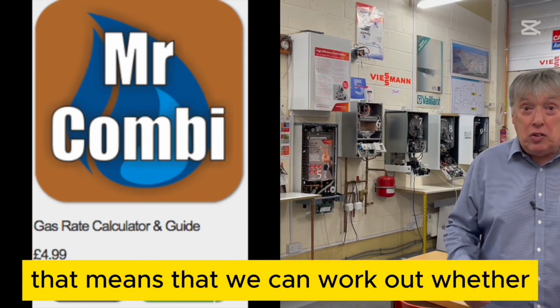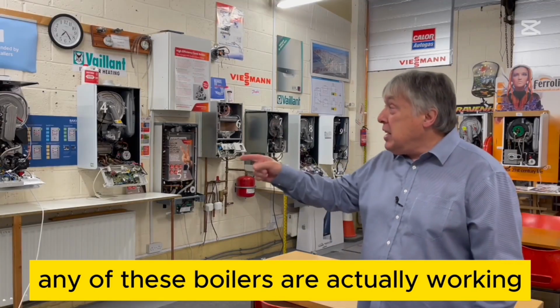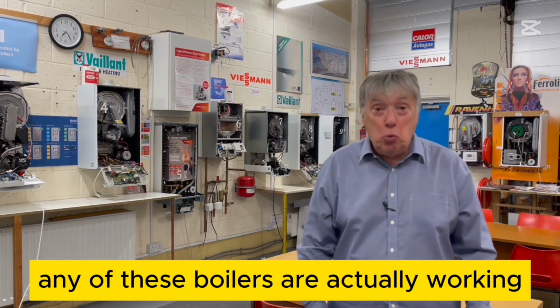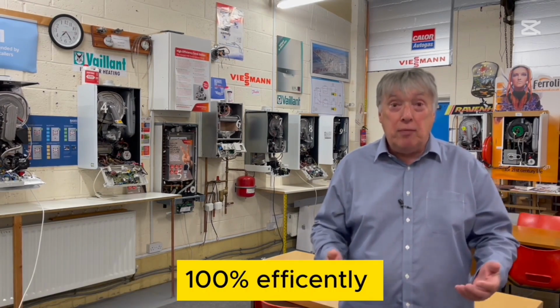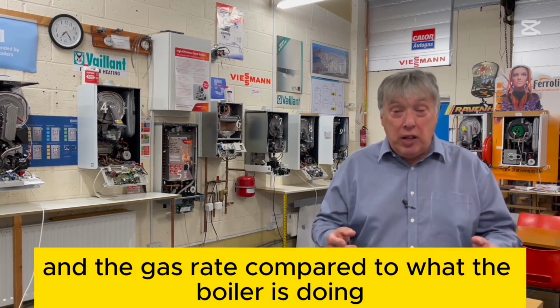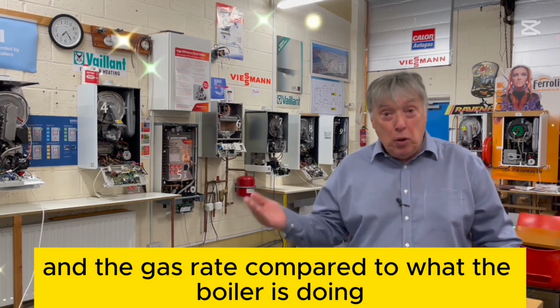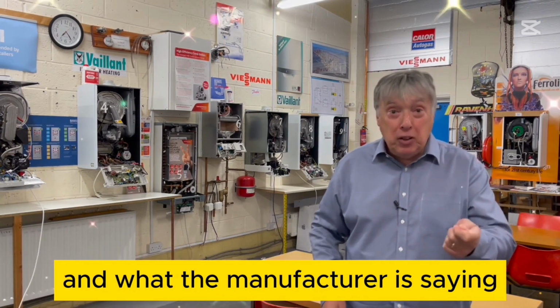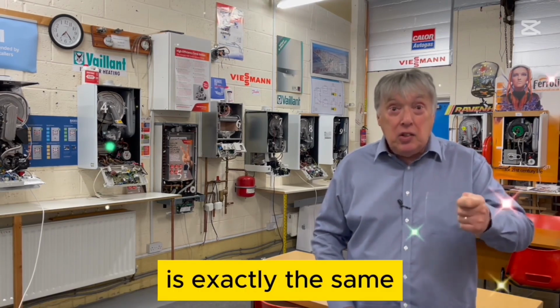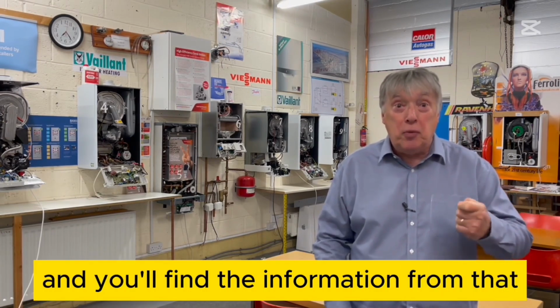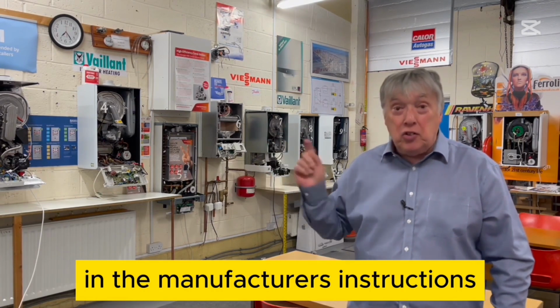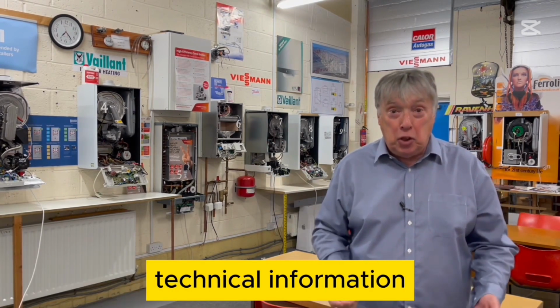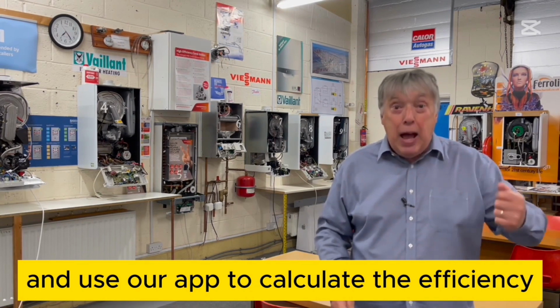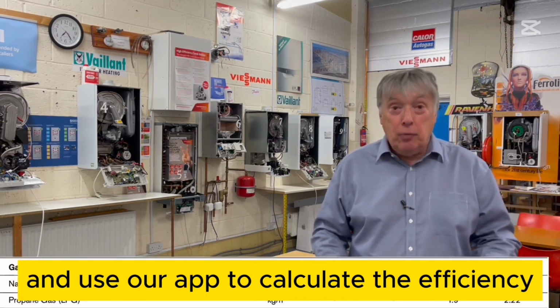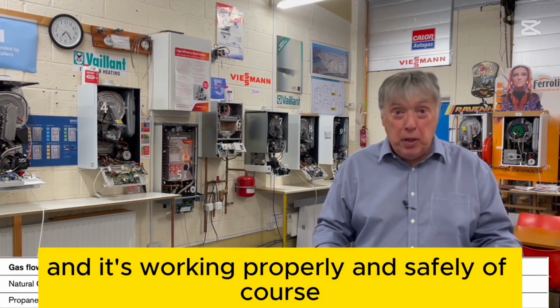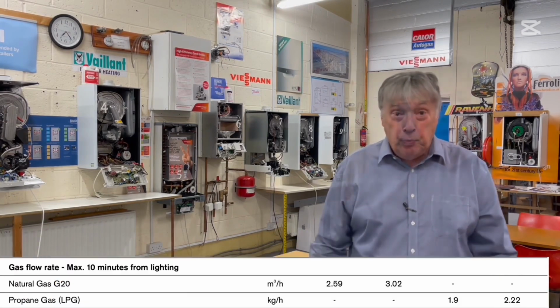So that means that we can work out whether any of these boilers are actually working 100% efficiently, and the gas rate compared to what the boiler is doing and what the manufacturer is saying is exactly the same. And you'll find the information from that in the manufacturer's instructions, technical information, and use our app to calculate the efficiency and it's working properly and safely, of course.